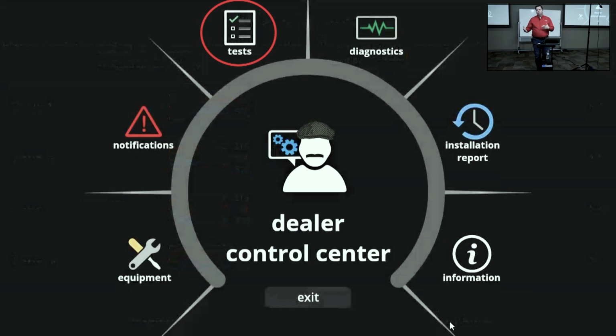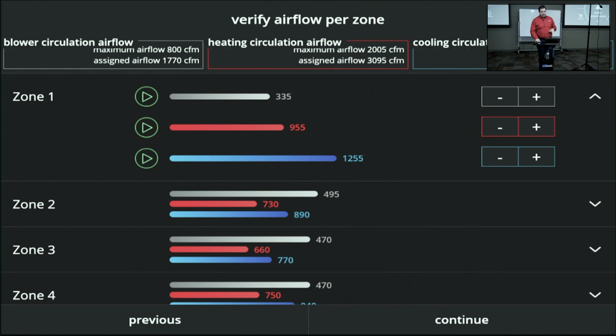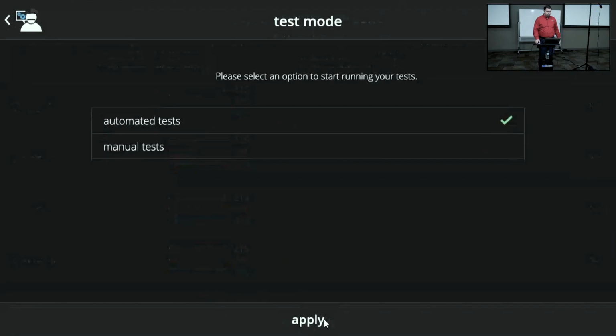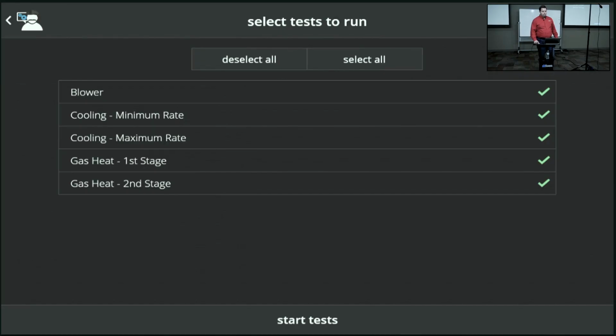When you go into the installer setup mode, you can look at the input on all your sensors and all your communicating components and see the status. That won't shut the unit down. It won't interrupt your call, so that can be handy. But when you're doing initial startup on these, you can select that test option, and it's going to take us to the zone CFM setup screen here. So you can make adjustments for your heating, cooling, constant fan airflow for each one of these zones. And then it will take you through a test mode. You can either do an automated test or manual test.